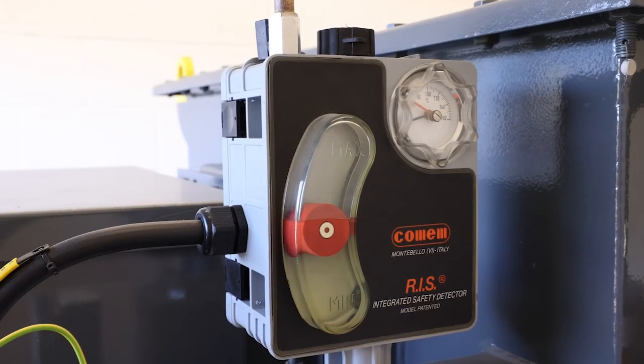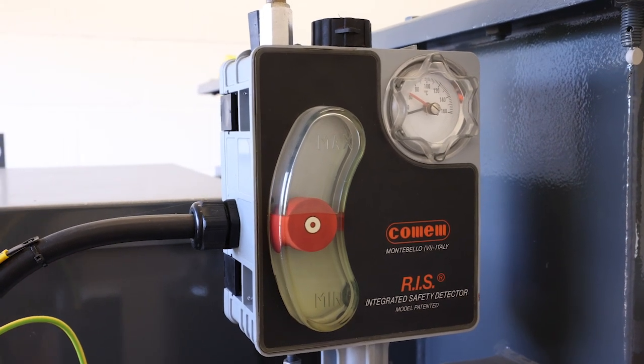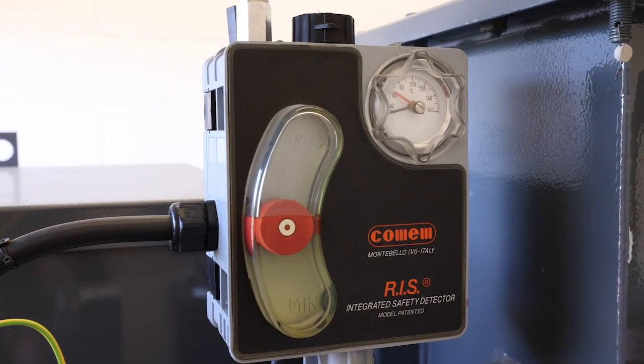Well, I guess it's easy to spot oil on the floor. Well, the oil might leak out onto the floor, but if the transformer is in a bund or an area that's hard to see, any leaks won't be so easy to spot. What you can do is check the sight glass on the side of the transformer. This shows the oil level so you can see if it's lower than it should be, which would suggest a leak. If there's anything though you're not sure about, check with the site personnel who can advise you.